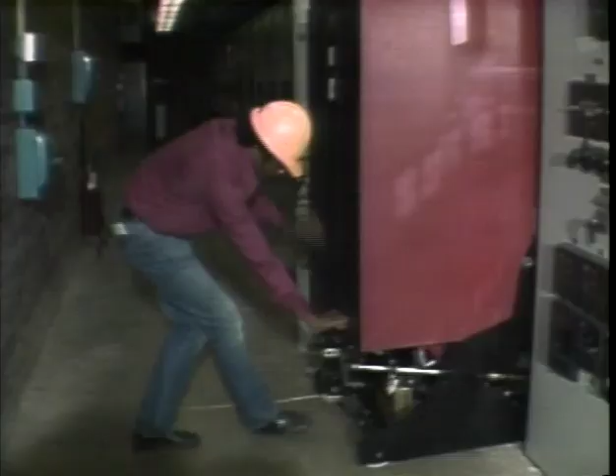Air circuit breakers use a blast of compressed air to extinguish arcs. This simplified illustration represents the inside of an air circuit breaker. Its components include two switch contacts, an air blower, and a protective housing. Now, the air blower and switch contacts are timed to work together. When the switch contacts are opened under load, the blower releases a blast of air at the space between the contacts. This extinguishes the arc. Whenever the breaker is opened, this same process occurs.